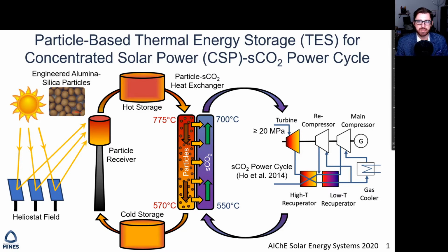Here, I show a schematic of a solar-driven sCO2 power plant with particle-based thermal energy storage. On the left, solar heat is stored in particles as they pass through a particle receiver. The heated particles feed the hot side of a particle-sCO2 heat exchanger, where the solar heat is transferred to the sCO2 working fluid that drives the Brayton power cycle, like that shown on the right. The cooled particles are then stored and recycled back to the particle receiver.